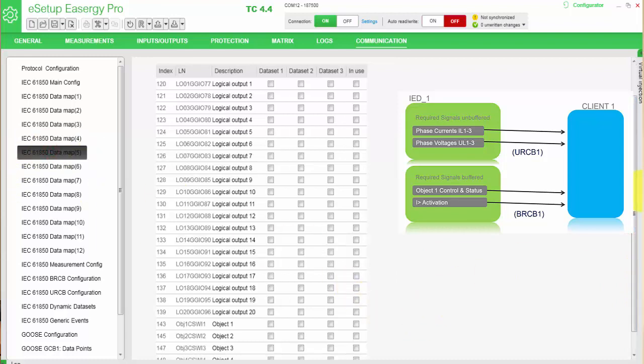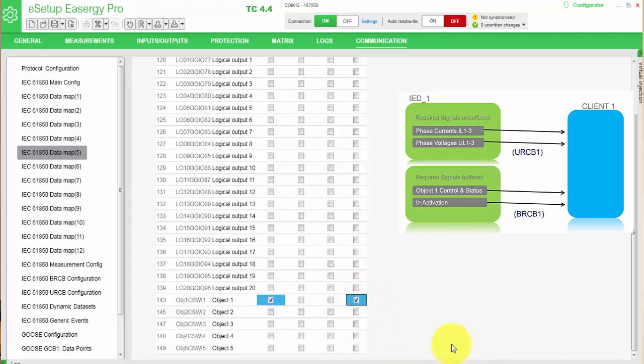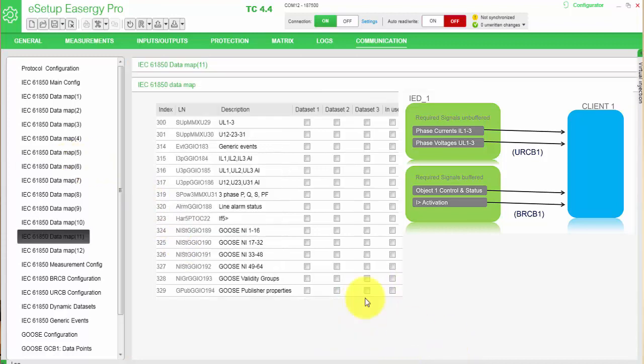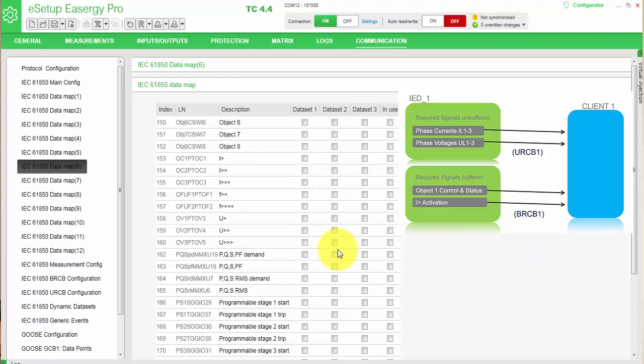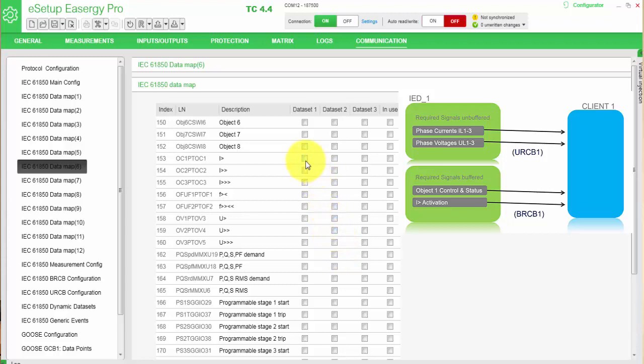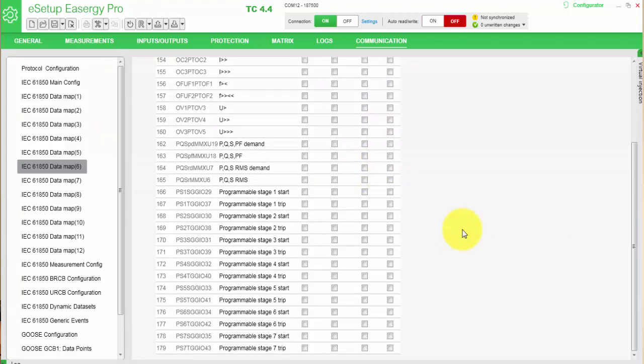From page 5, you can find object 1. We will define that as a buffer, so we will put it in a separate dataset. We will put object 1 in dataset 1 and we will choose it in use. On page 11, we will have the voltages, so we will put it also in dataset 1 to have it as a buffer and we will put it in use. On page 6, we have the overcurrent function, and we wanted to have that in the buffer control, so we will activate it in dataset 1 and put it in use. And now we have selected all the signals we need.